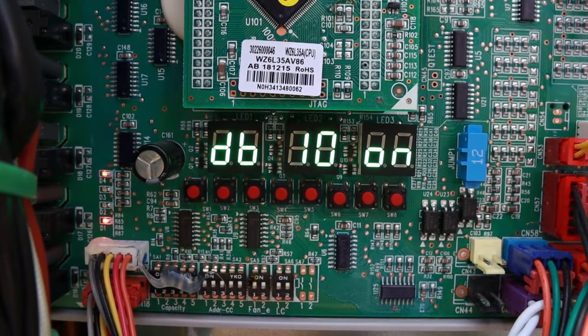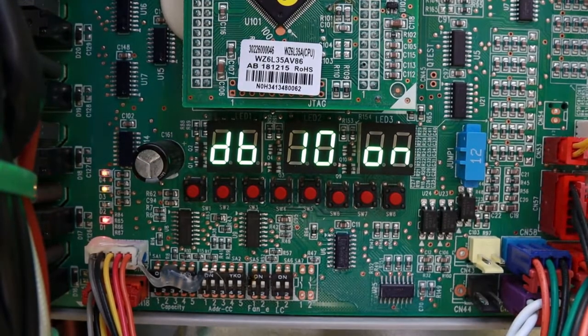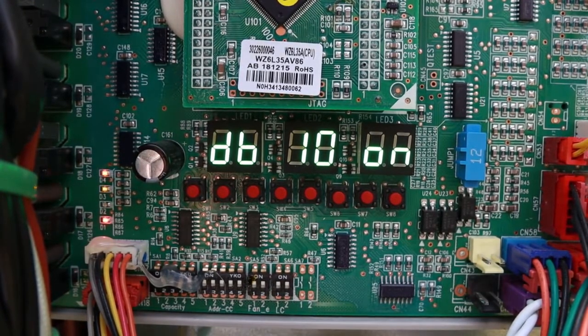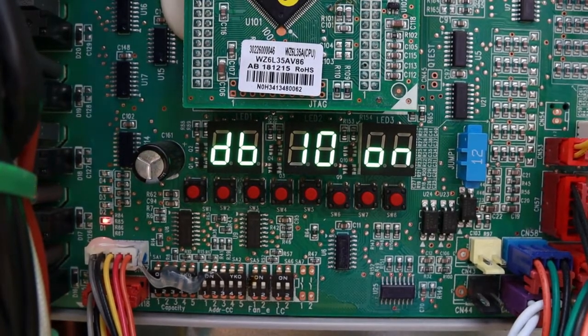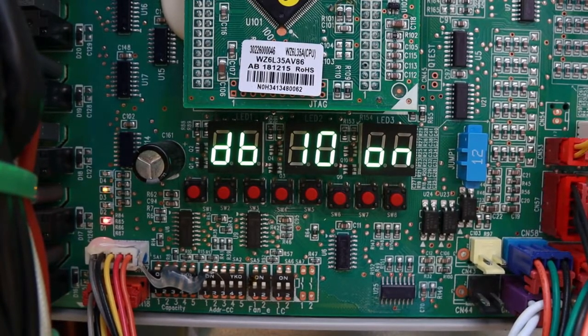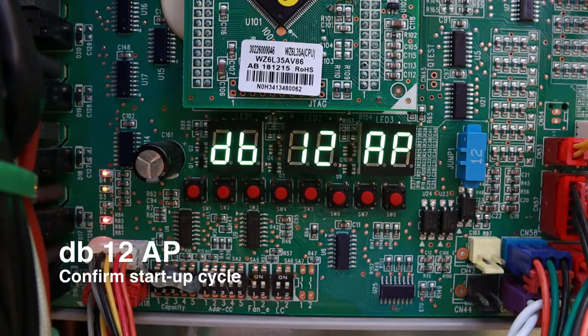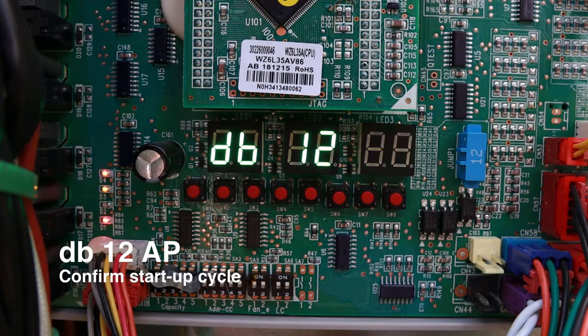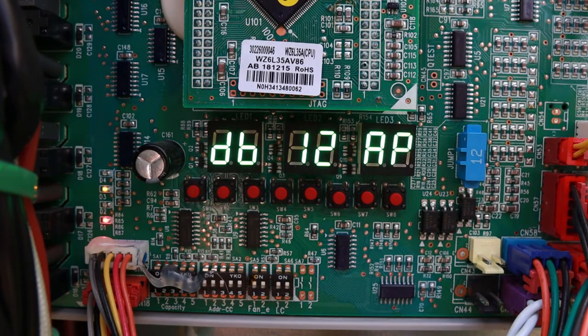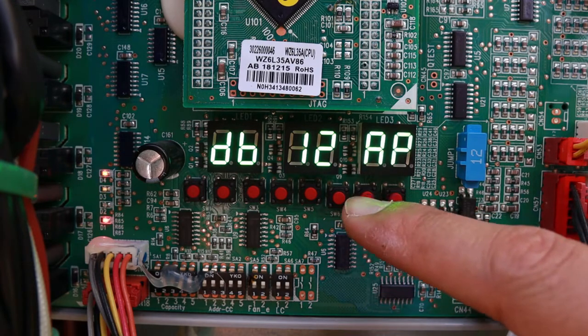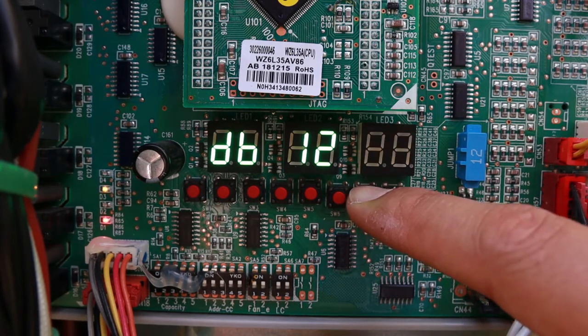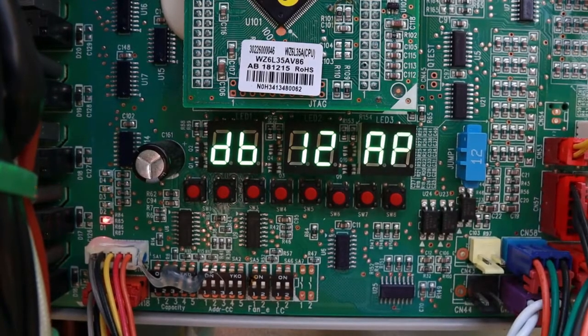Make sure that you open the valves before you start the commissioning cycle. Otherwise, you're going to have an issue here. So do that before you start the commissioning. And then when you get to step 10, just let the system run. It will take again about 5 minutes or so. And then you will see that the system will jump automatically to step 12. On step 12, the system is asking us to confirm that we're ready for the startup cycle. So in this step, we're going to go ahead and press SW7 to confirm. We're going to press it once, and then we'll see how it jumped automatically to step 15.